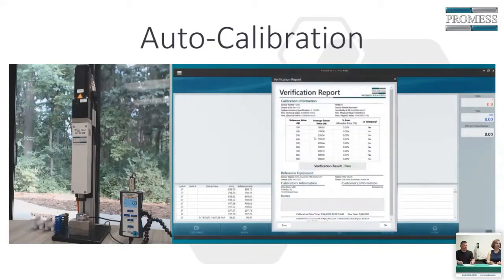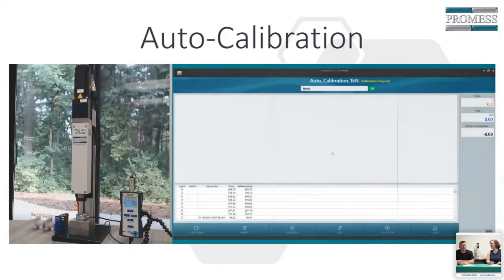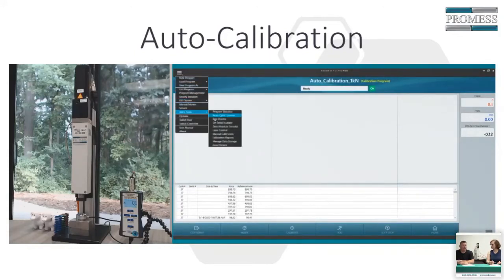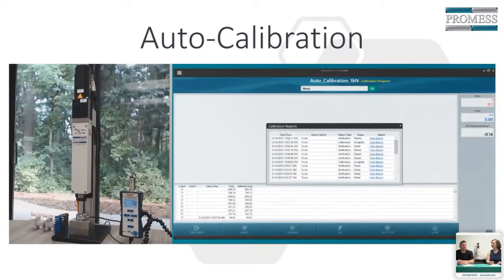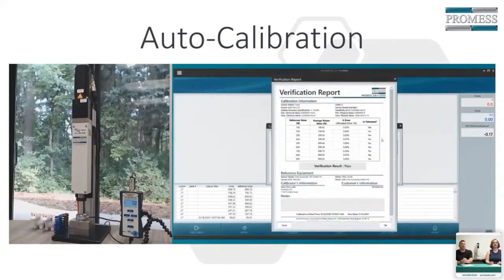On this verification report, we can see that our error is well within the 1% limit, and our report shows a passing result now. If we want to look up a previous calibration or verification report, these can be found in the More Tools menu under Calibration Reports. This shows all of the passed and failed verification cycles as well as the adjustments made. This can also be saved as a PDF or notes can be added for later.